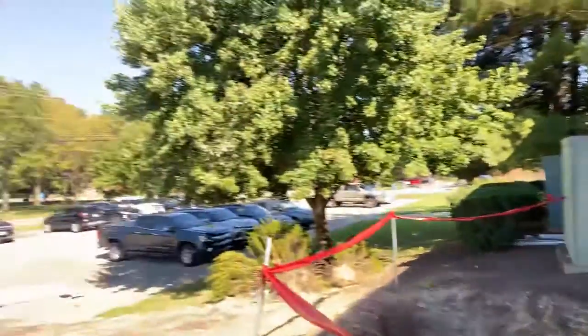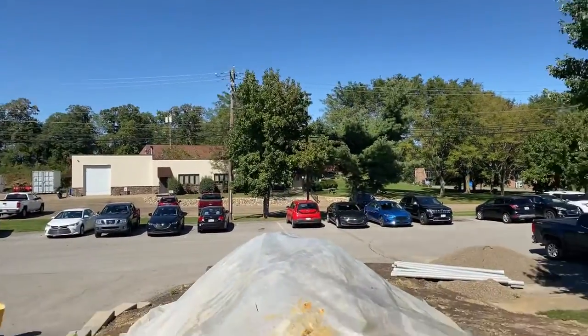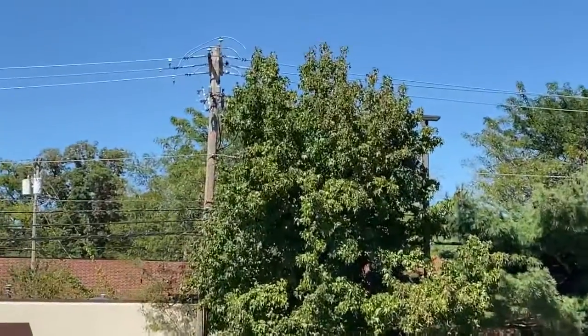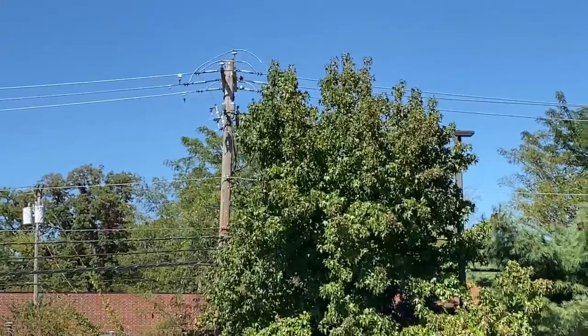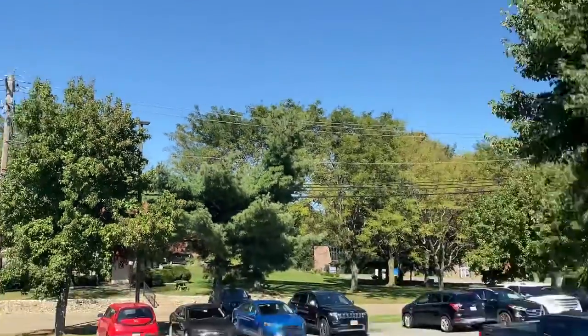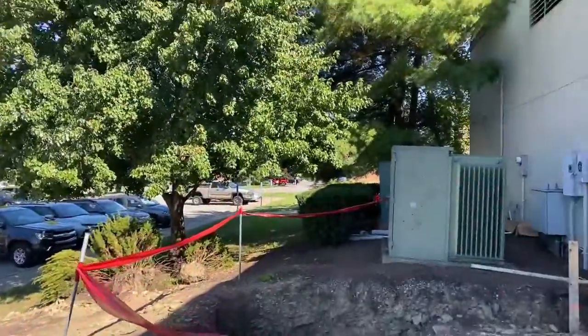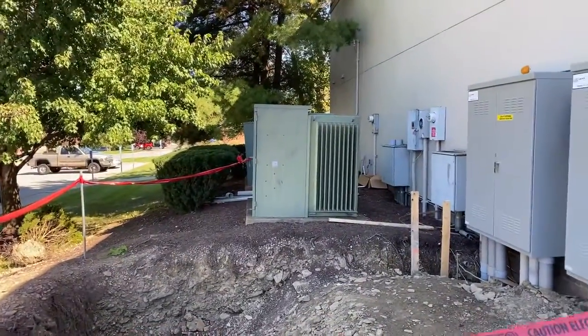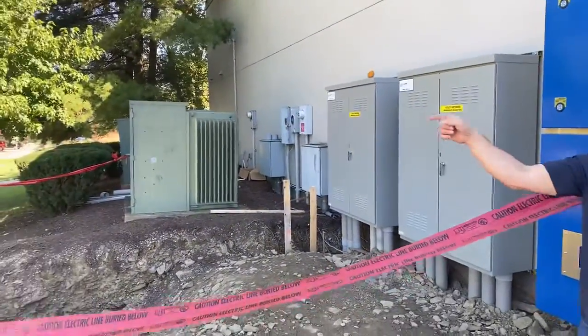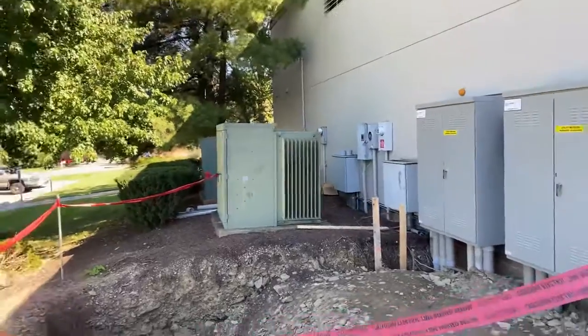I don't know if you can show the pole up there, Tom. Yeah, the fused cutouts up there. So if we were to turn power off in the building to do any work at all on our switchboards, we've got to get the utility to come out, turn off that set of fused cutouts so that we can turn off those two transformers over there, and then get inside the building and do our work.